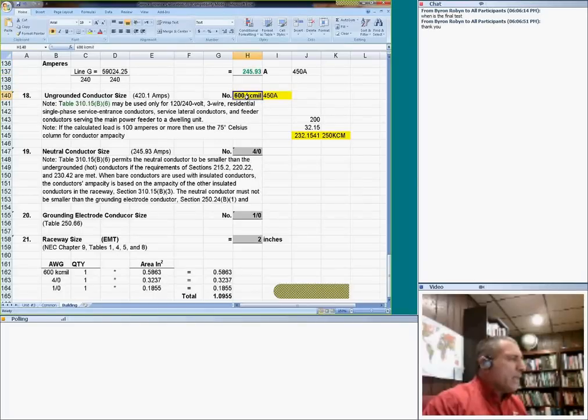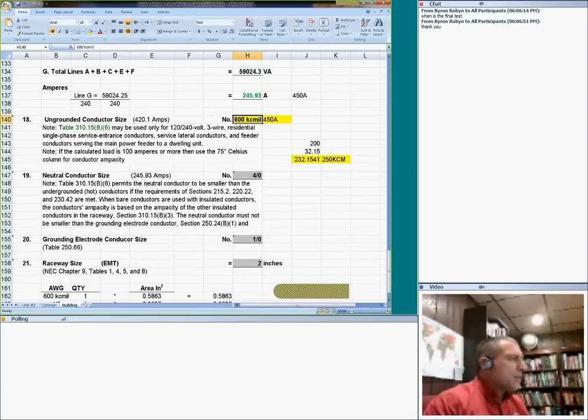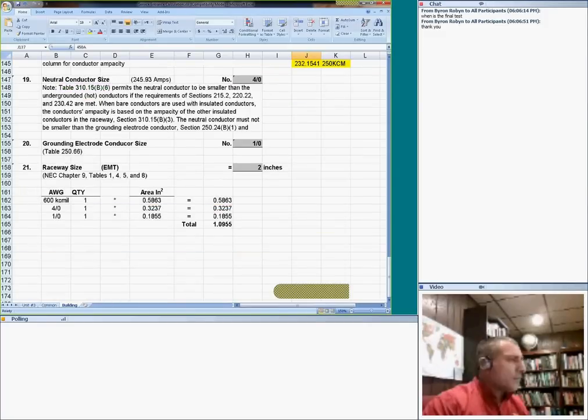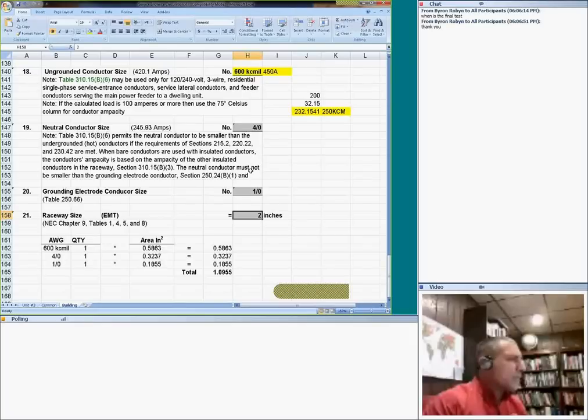Okay, you start with your conductor, 600 kcmil, 2 conductors, and to carry the neutral 240, I believe 4/0 could get you. So you have 4/0 and 600 kcmil. Neutral for us, 600 kcmil should, if I'm right, get you to carry a 450 amp panel. 400 amp panel. And then you get into sizing the EMT conduit, guys. You get into sizing, how to size the conduit for it. There's the size you end up with. I don't know if we did right, so don't look at this one really. 2 inches. I think 2 inches sounds small for 2 conductors plus that one.